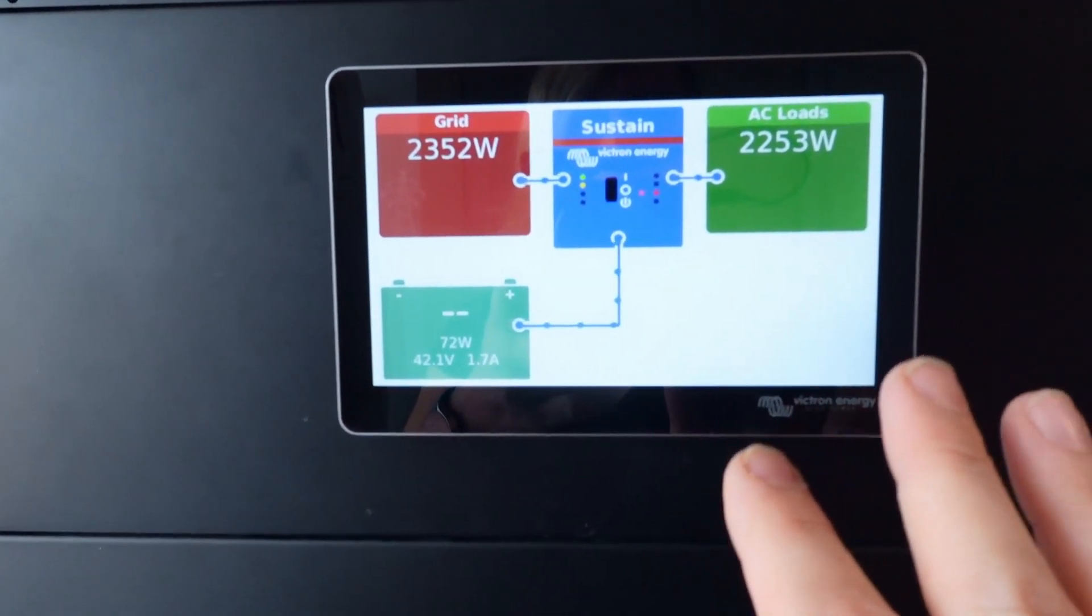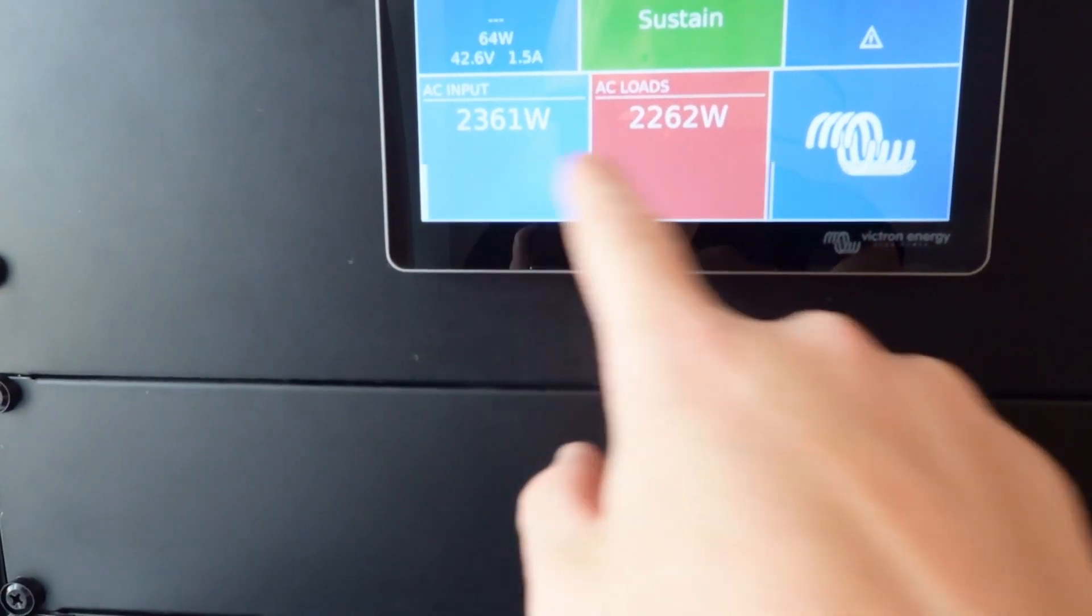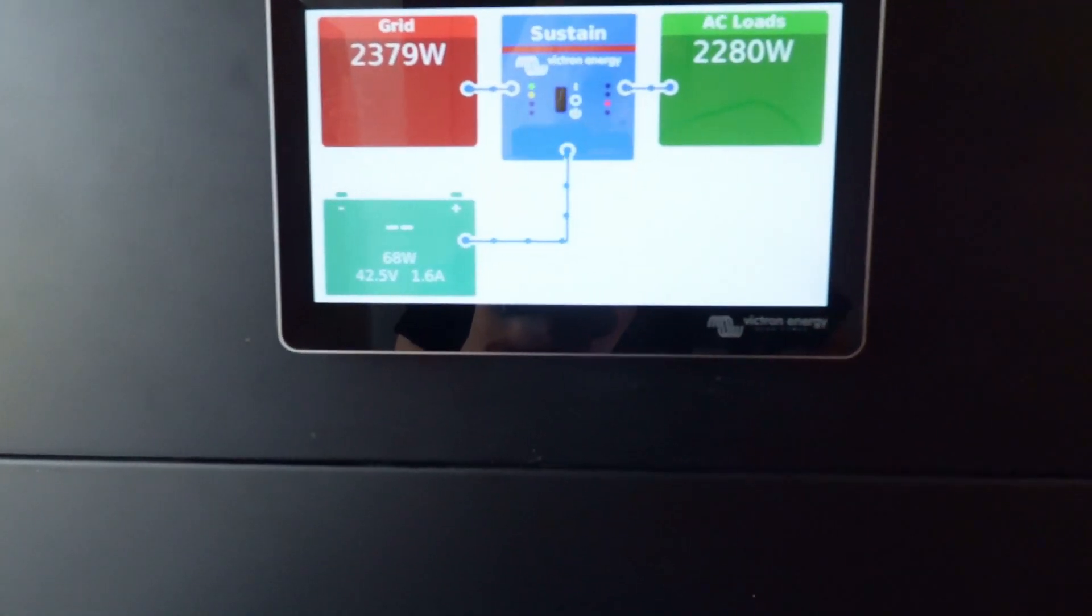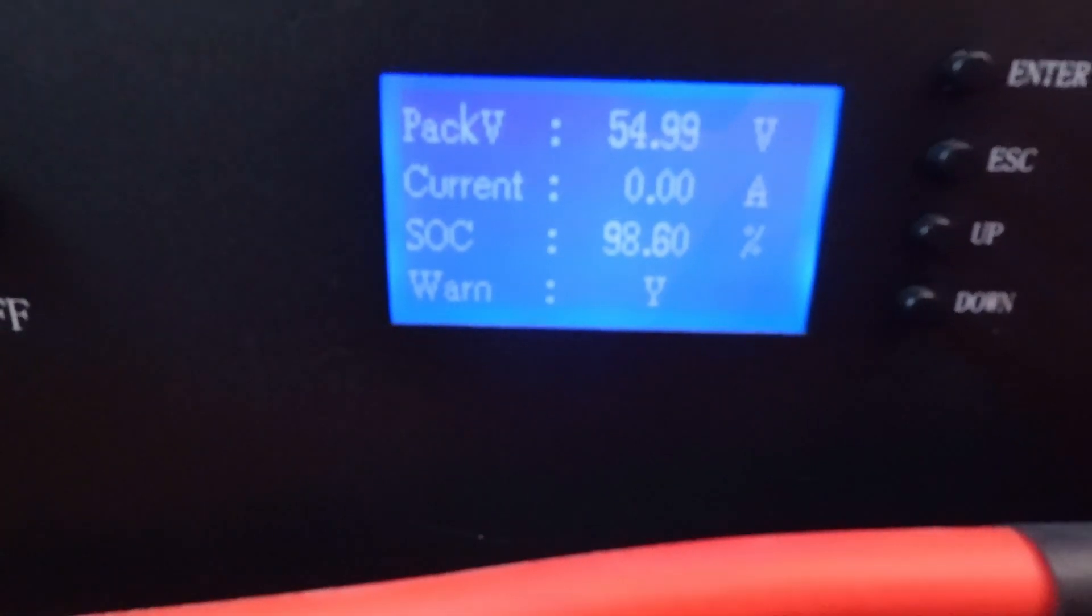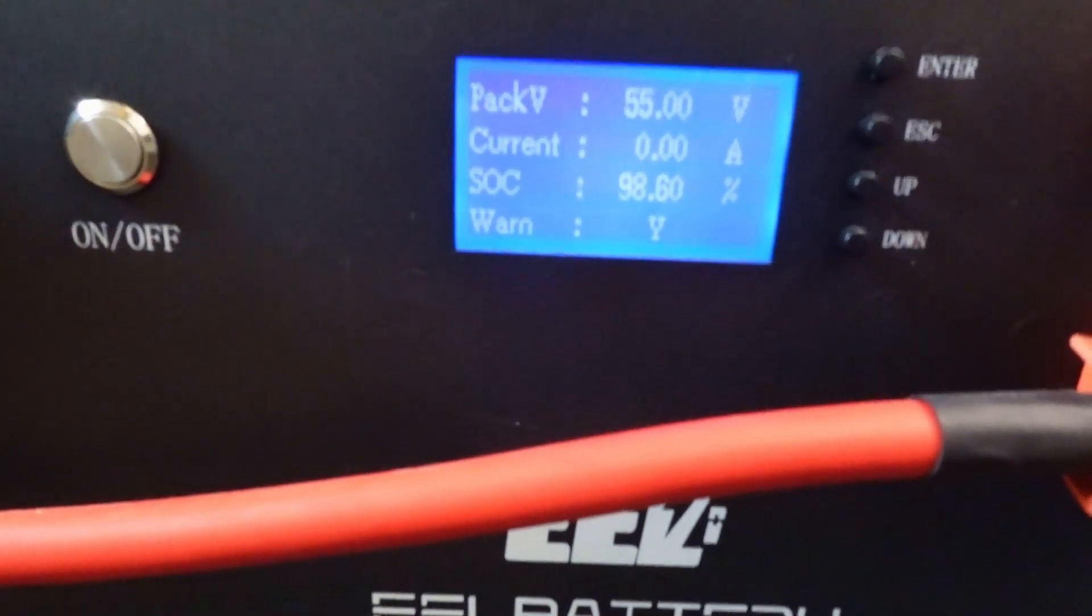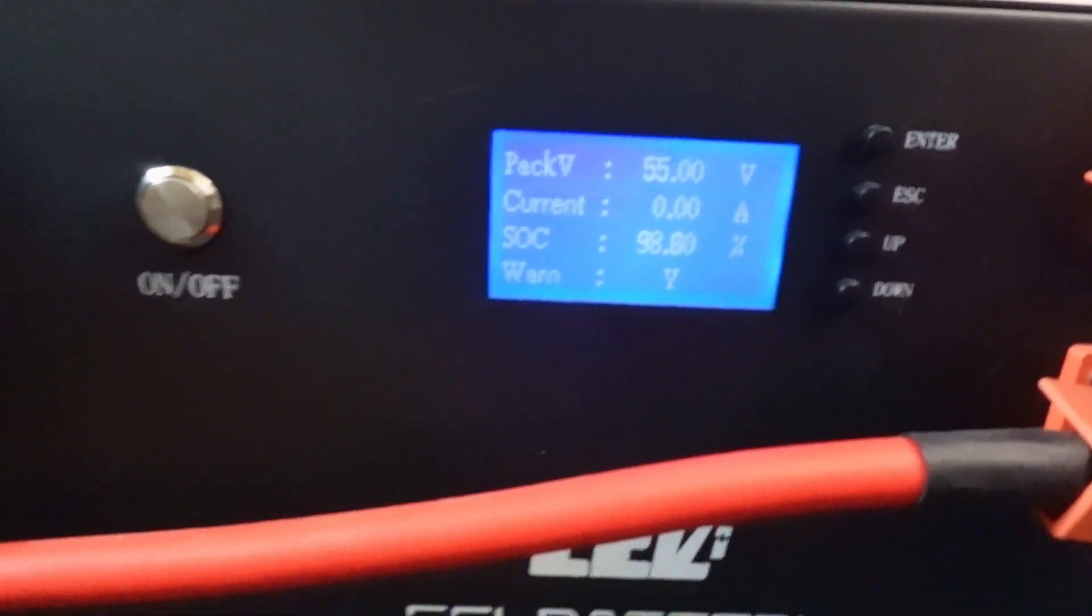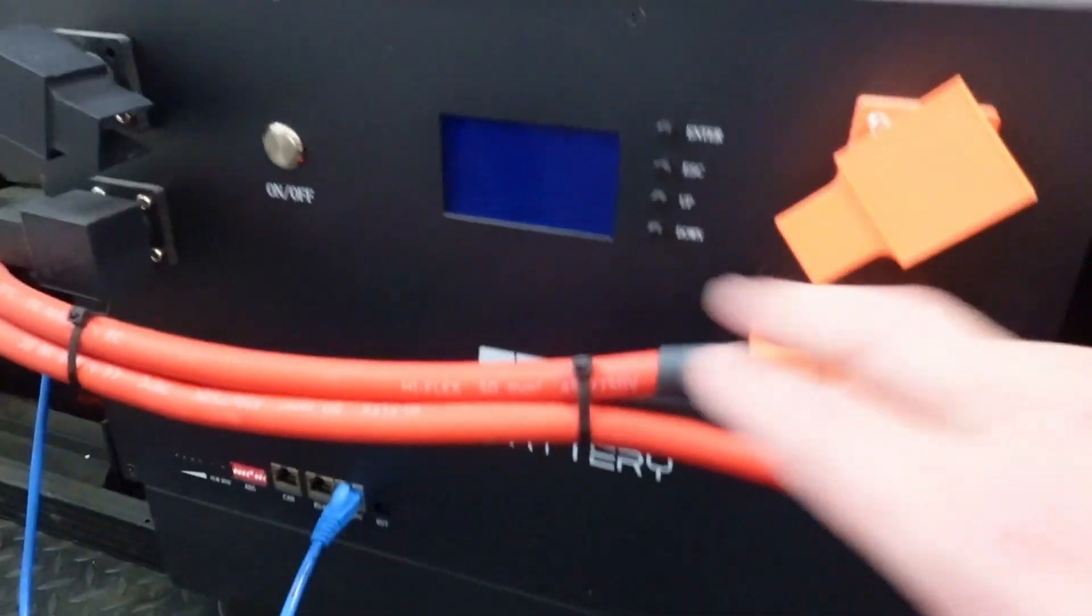I've shut those down and now we can see the solar system has gone, the battery we've got nothing. Let's have a look. There we go, for some reason it still has a little graphic there even though I've disconnected it but yeah so basically that now has shut down. If we actually look on the actual display here, this is the working battery, we can see here it says current zero amps. So we know that there's no current going in or out of the battery, obviously it can't because we physically disconnected it. Obviously this battery doesn't have the working display. It does still work because we've got the status lights at the bottom there.